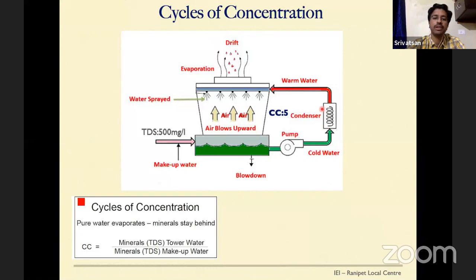Again, it's pumped out into the cooling tower. It goes to the condenser, takes up the heat, then dissipates the heat in the cooling tower and comes back again. This happens up to some number of cycles. That is called the cycle of concentration. What happens is the pure water normally evaporates and whatever minerals are in the water stay behind. So ultimately we are sending out pure water, leading to a higher concentration of impurities, that is dissolved and suspended impurities, in the cooling water cycle. So the TDS keeps on increasing, up to 5 times, which is called 5 cycles of concentration.